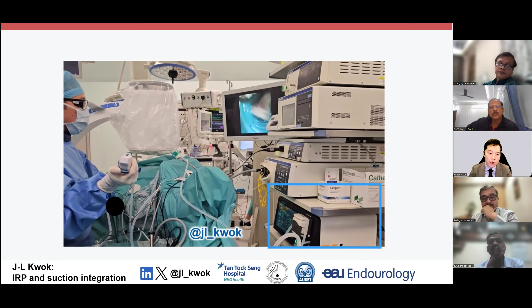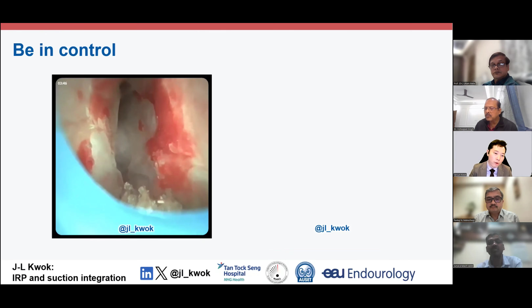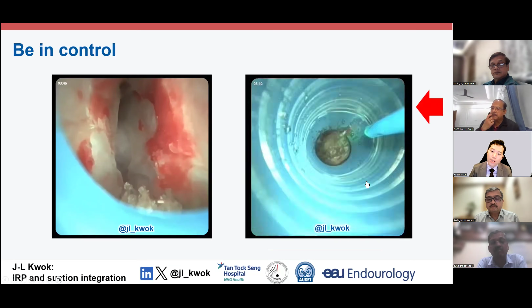So in this case, I went up with a FANS sheath, and the first thing I saw was that it was totally collapsed. And I was wondering why, because the pressure was super, super high. It was like 90s to 100s. I wondered, why is the IRP so high despite it being collapsed? So the first thing I did was remove and take off the IRP monitor. I was trying to troubleshoot, and I found that if you look at the right-hand side at 2 o'clock, there was a piece of tissue stuck in the IRP monitoring aperture, and that caused an artificially high pressure. Therefore, I think it's also important as you use your machines, whichever system you use, to know how it measures the pressure, as well as what it does when pressure is high, so that you're able to troubleshoot.